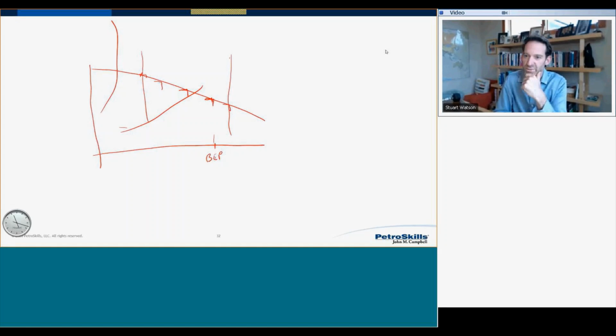There is a difference in opinion when it comes to suction velocity. Some experts say that as long as you keep the NPSHA greater than NPSHR, you don't need to worry about suction velocity. And this starts a whole lot of very interesting dialogue about these terms. The first thing that I would say is, as long as we all realize that if you're operating where NPSHR is approaching NPSHA, you're operating with the pump cavitating.